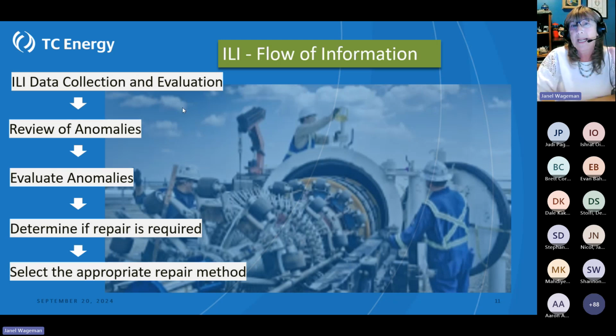One of the ways that we ensure the ILI data is correct is we have what's called a calibration spool, which is about a 6-meter length of pipe that has had defects machined into it. You need a thicker pipe than this on either side, because you're losing wall thickness by machining in these various defects. But we know exactly where the defect is located—it might be a pinhole or a little slot. When the ILI tool picks up those spots, we can say the data is accurate because it saw exactly the location and depth of this pinhole or defect. So that's one way we verify our information.